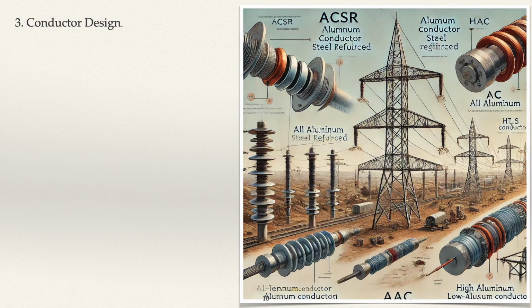Conductor design. It involves selecting and configuring the appropriate conductor material and structure to efficiently and safely carry the electrical load while withstanding environmental and mechanical stresses. 1. Material selection. Aluminum is widely used due to its lightweight and good conductivity. Copper has higher conductivity but is heavier and more expensive than aluminum. Composite conductors are modern materials like aluminum conductor composite core, ACCC, or aluminum conductor composite reinforced, ACCR, used for high-capacity lines. Steel-reinforced conductors, aluminum conductor steel-reinforced, ACSR, combine aluminum for conductivity with steel for mechanical strength.